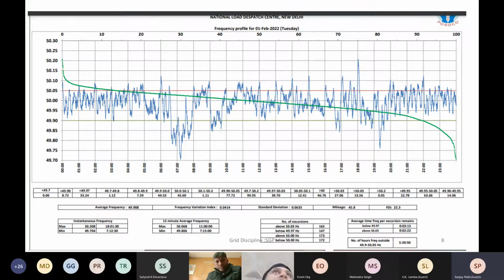This is one of the latest reports from the National Load Dispatch Center, where you can see how the frequency fluctuates. This is the 49.9 level, and this is the 50.05 level. So this is your operating band. You can see how the frequency is getting controlled within this narrow band. There are some excursions, and this daily report actually gives the number of hours the frequency is outside this band. In a 24-hour day, the report says that for 5 hours the frequency has been outside this band. But this is a remarkable achievement of the Indian power system with its growth, that we have been able to operate frequency in such a narrow band, just like power systems in developed countries like in Europe and others. We are almost now at par with those power systems.